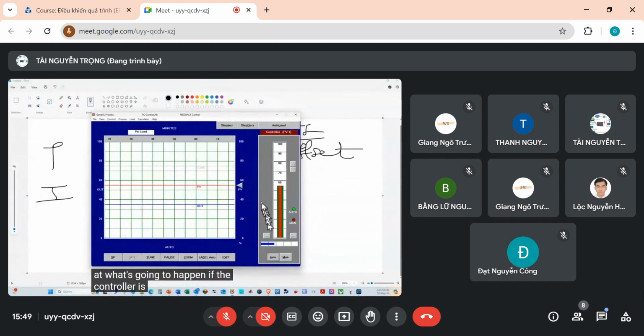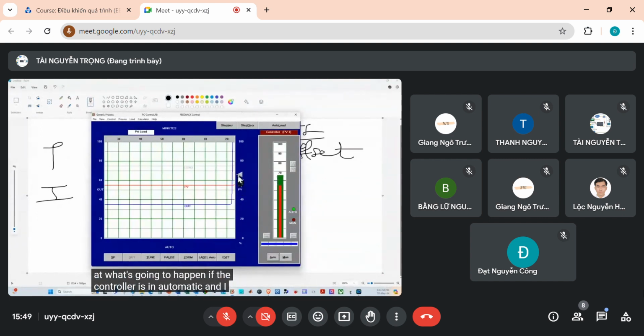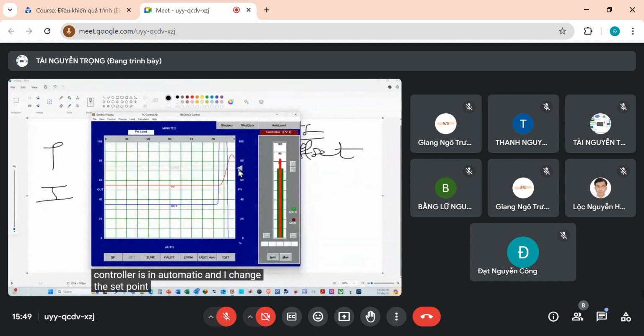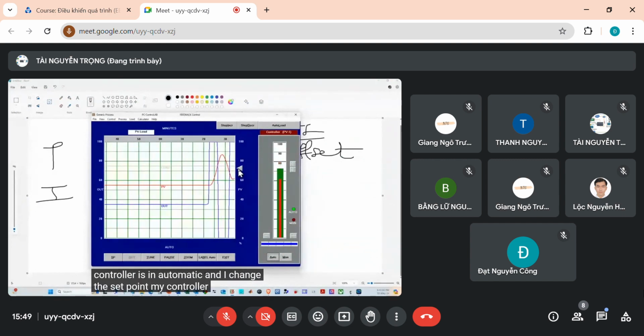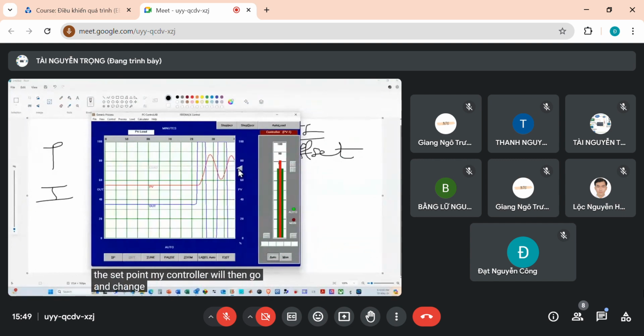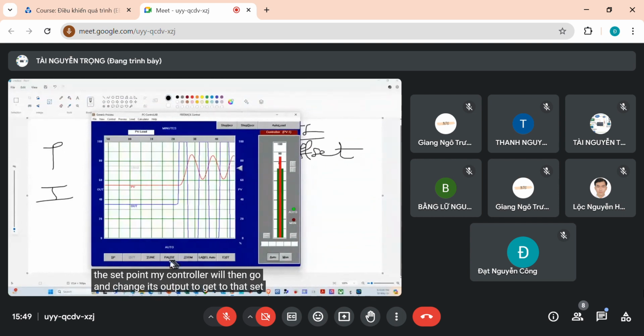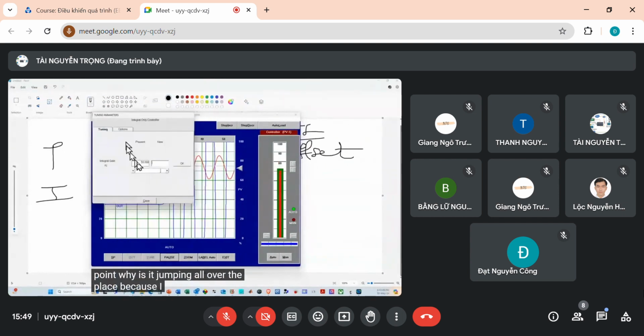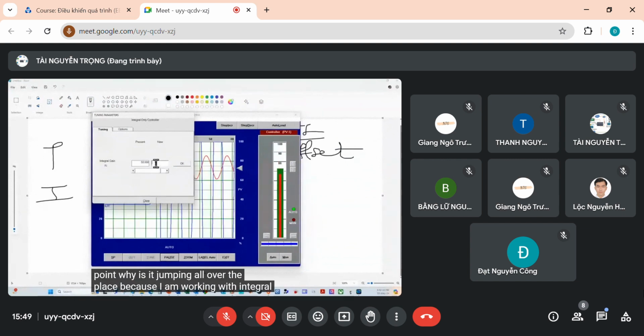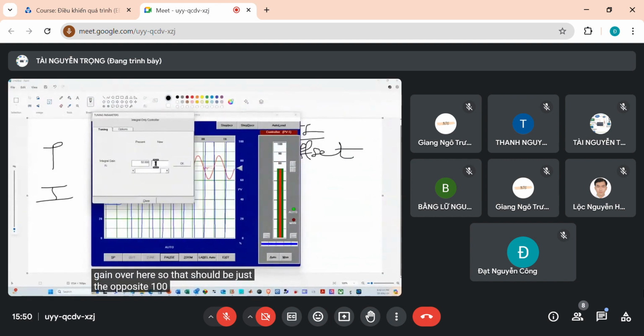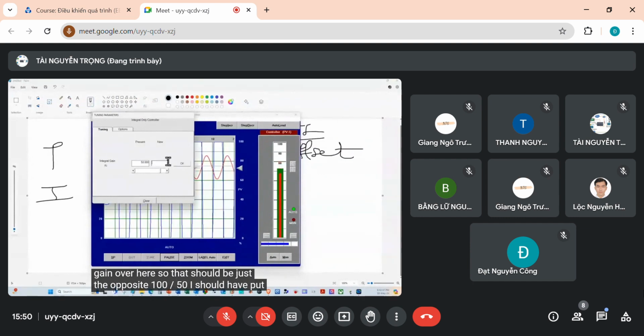If the controller is in automatic and I change the set point, my controller will then change its output to get to that set point. Why is it jumping all over the place? Because I am working with integral gain over here. So that should be just the opposite - 100 divided by 50, I should have put in a value of 2.